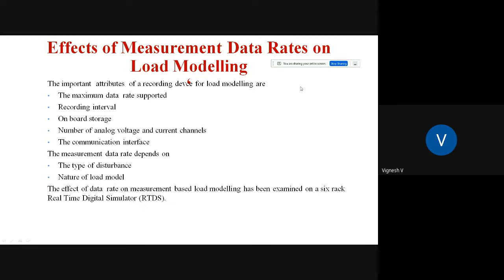So this gave rise to another study that we made using PMU and the RTDS to see what data rate we need when we try to obtain the data. For example, if you get data at a very high rate and you don't have storage space, and you don't need that accurate dynamics, then there is no point in getting the data at that rate. So as a recording device, a PMU or a fault recorder should have some important attributes, like what is the maximum data rate that it can support, what is the recording interval, and what is the onboard storage, the storage that you have on the recording device itself. The measurement data rate also depends on the type of disturbance and the nature of the load model. So now we are going to see what type of disturbance and what type of load model affects the data rate. Data rate means the rate at which you get the data from the sensing device. Next slide, please.